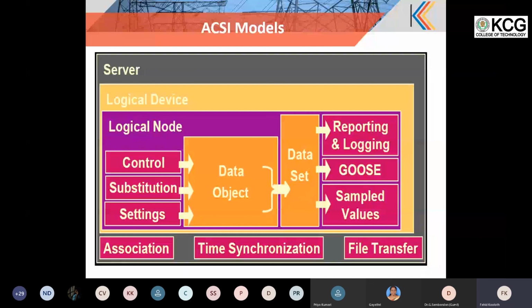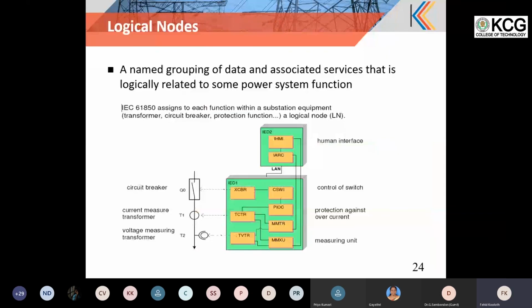Now this is a logical node, a distributed logical node. As I mentioned, it can be distributed over multiple IEDs, multiple places. So an IED can have a circuit breaker function, then controlling the circuit breaker using the interlocks, then protection, overcurrent protection is there, measurement and metering logical nodes can be there, current transformer, voltage transformer, circuit breaker, all the things can reside in a single IED.